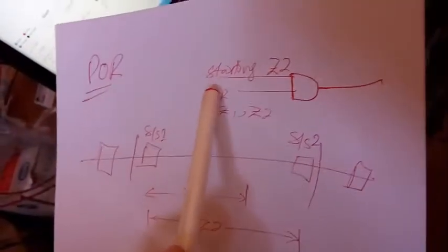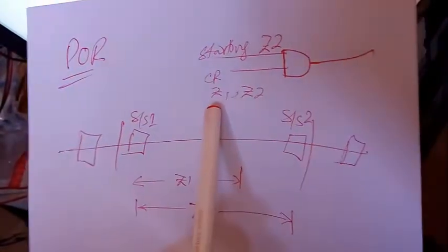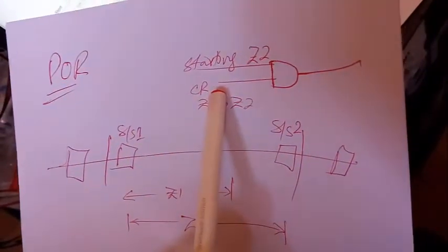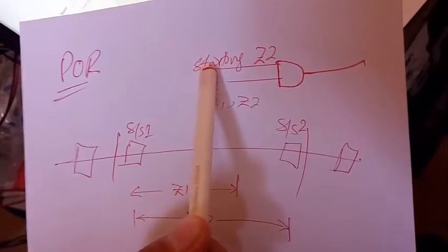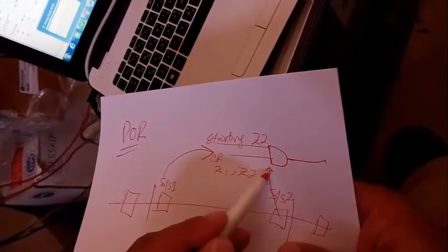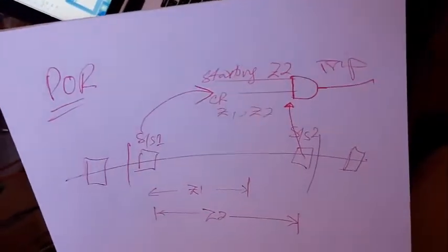This was all about the Permissive Overreach scheme. We have an AND gate with two conditions: starting zone two and carrier receive. For a fault in zone one or zone two, a carrier signal is sent. The receiving relay, with the AND gate conditions met, makes the trip. This completes the Permissive Overreach scheme explanation.